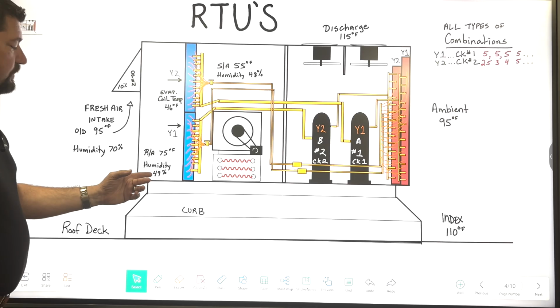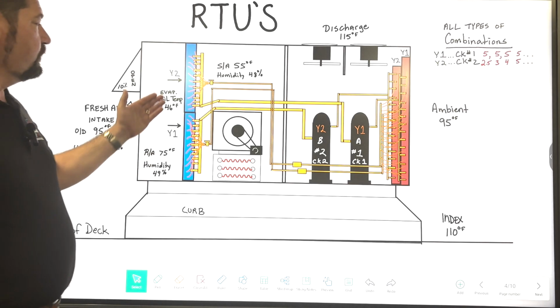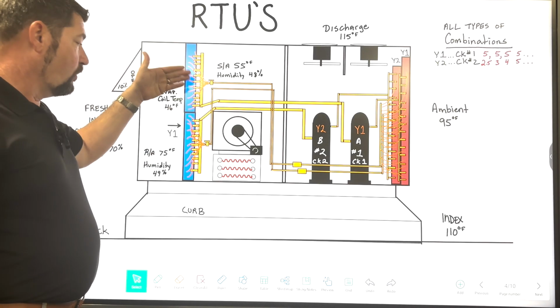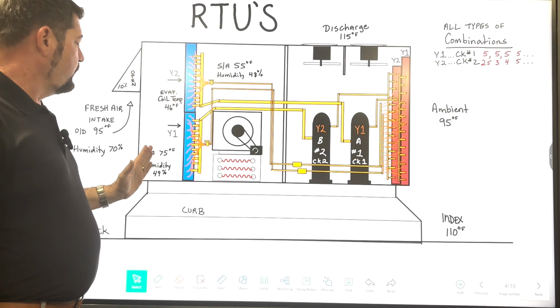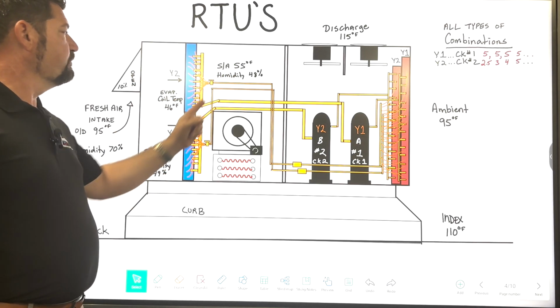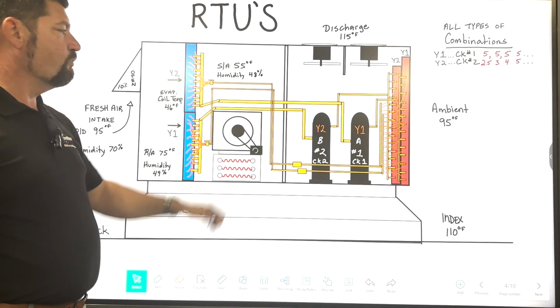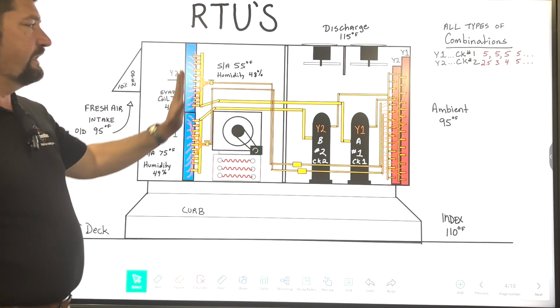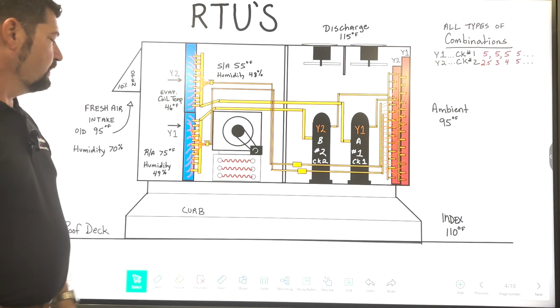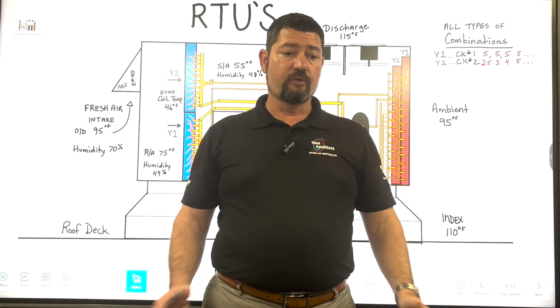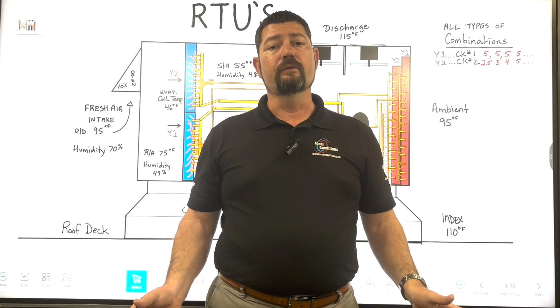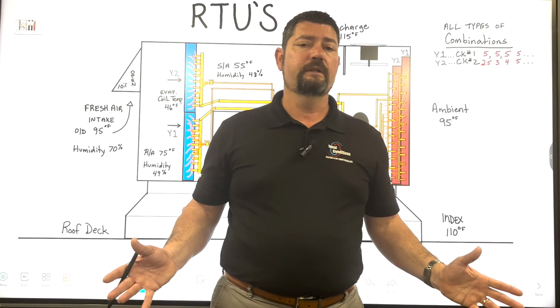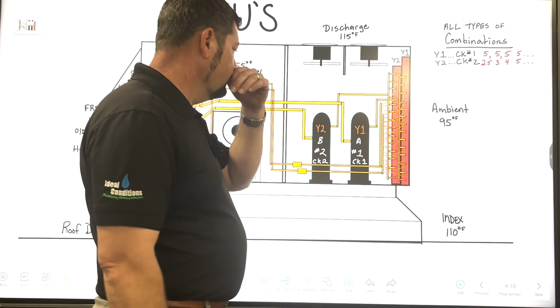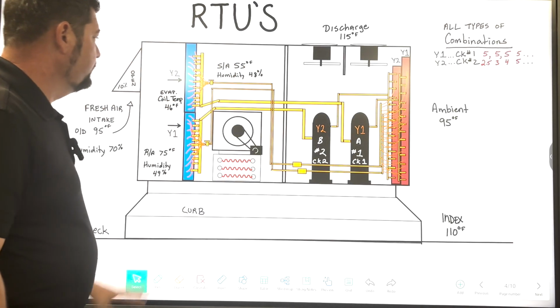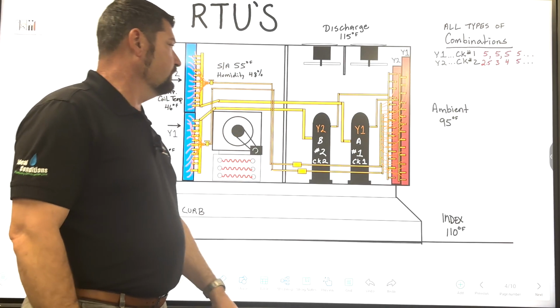So I have 49% relative humidity here going across that 46-degree coil, right? Obviously we're transferring a lot of heat, but we're not really removing a lot of moisture. So I just dropped it like maybe 1%, which is fine. Because if I had a room temperature of 75 degrees and the humidity was below 50% in a commercial building, I'm saying, hey, you're good to go. What else do you want? You're doing pretty good there. So nobody can really be picky there in a commercial application.